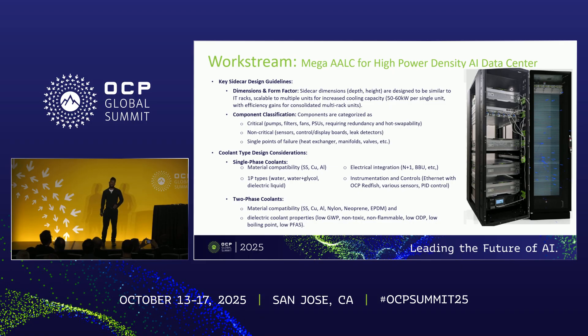The second work stream was the mega AALC for high-power-density AI. That presentation was done yesterday between AMD and Wiwynn. They built a prototype sidecar to match their theoretical data. The white paper is quite granular — it goes beyond performance to establish a baseline for a spec, covering dimensions, component classifications in terms of criticality, coolant type considerations such as two-phase versus single-phase, material compatibility, electrical and instrumentation requirements, and detailed considerations for deploying these different types of sidecars.